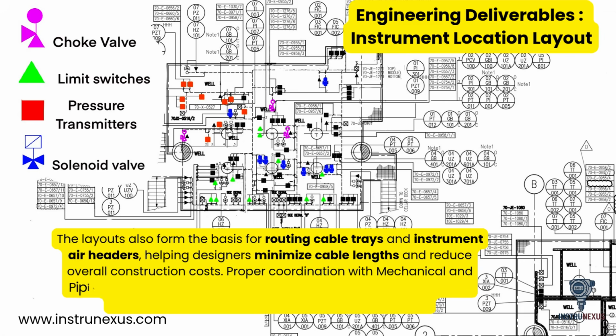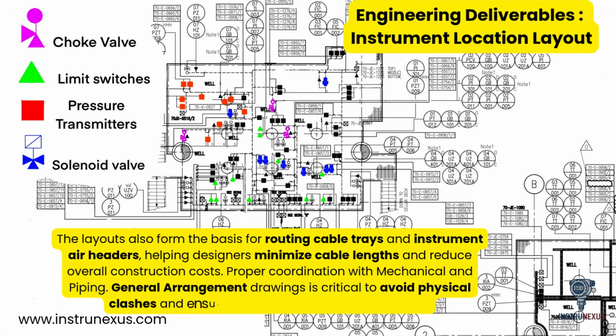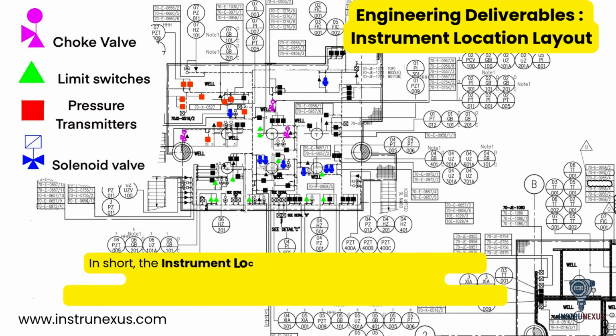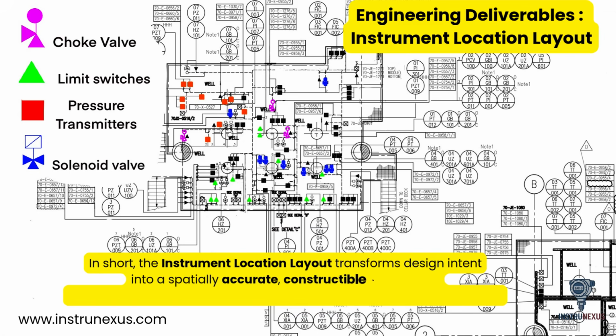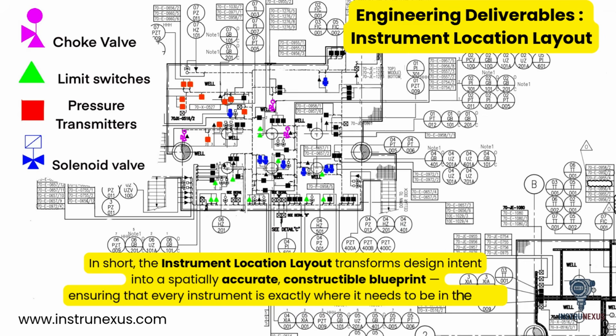Proper coordination with mechanical and piping general arrangement drawings is critical to avoid physical clashes and ensure safe, easy access for technicians. In short, the instrument location layout transforms design intent into a spatially accurate, constructible blueprint, ensuring that every instrument is exactly where it needs to be in the field.